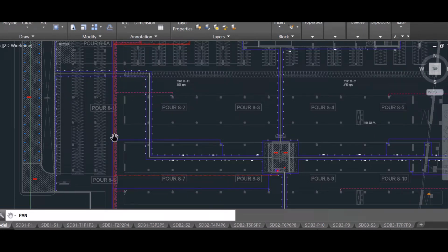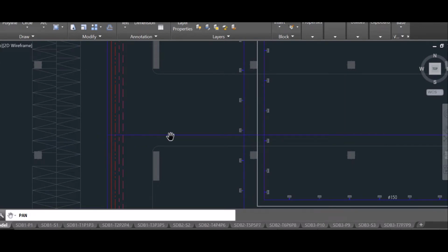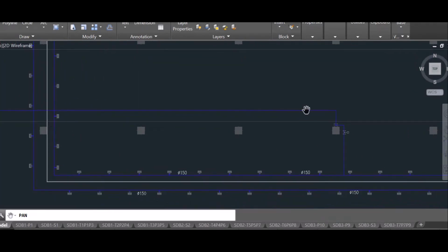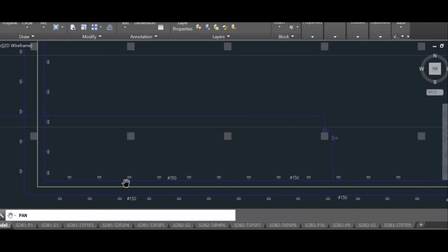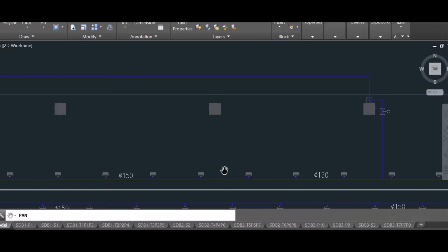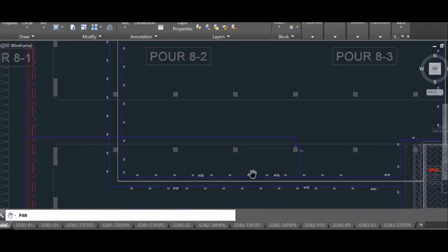basement, and from this ring main, for each individual zone, one individual tapping is taken here, and it's connected with a deluge valve and distributed through the periphery water main ring, which is connected with different numbers of nozzles.